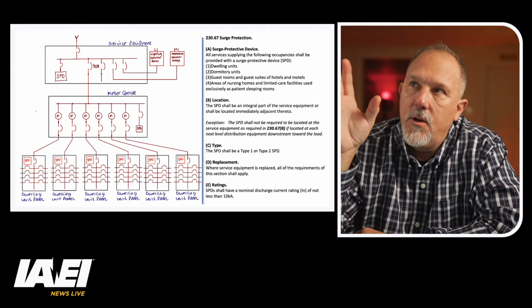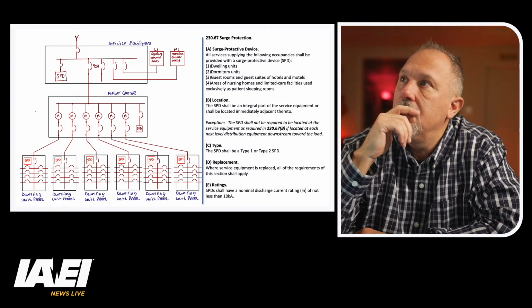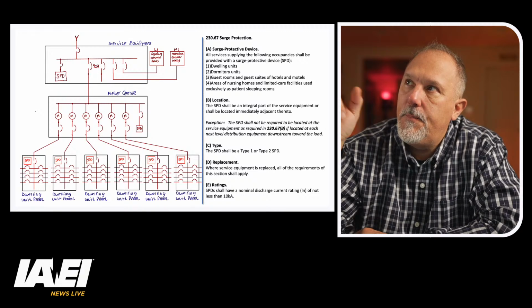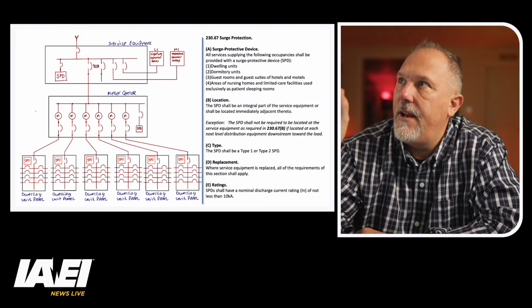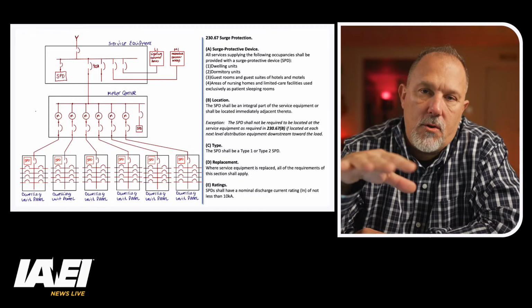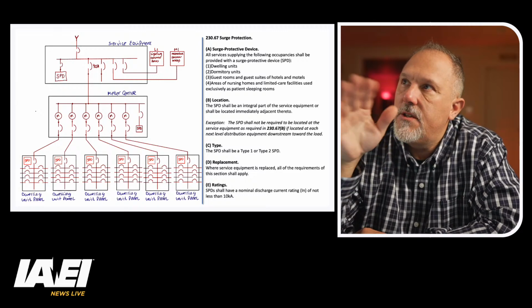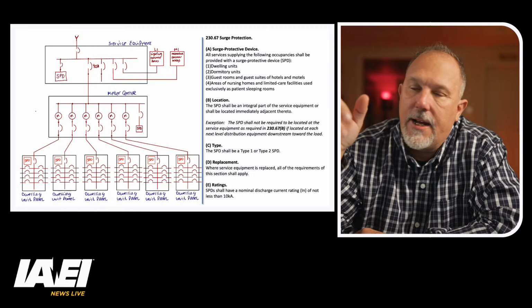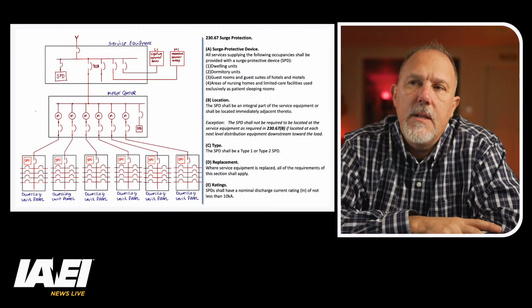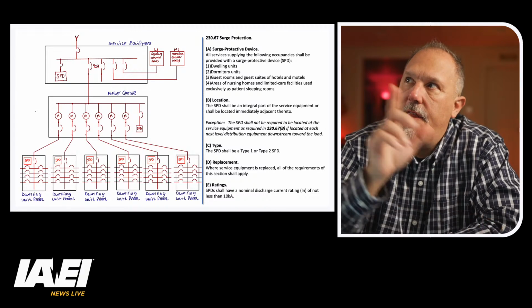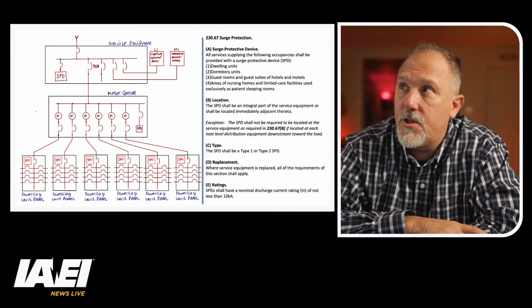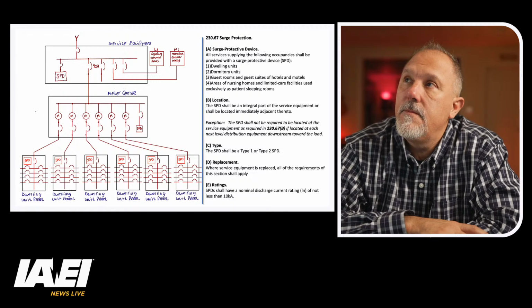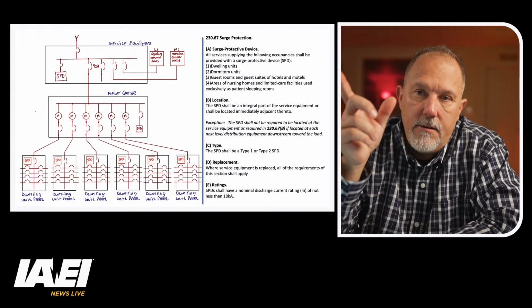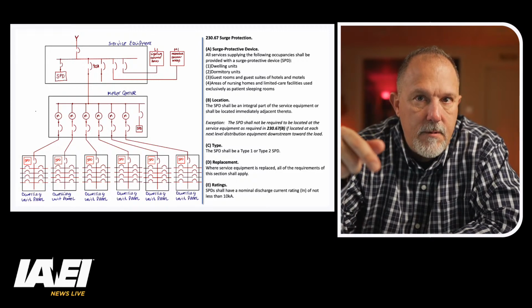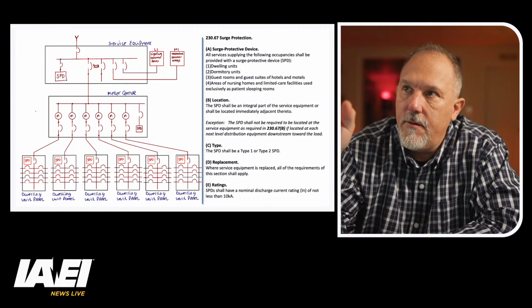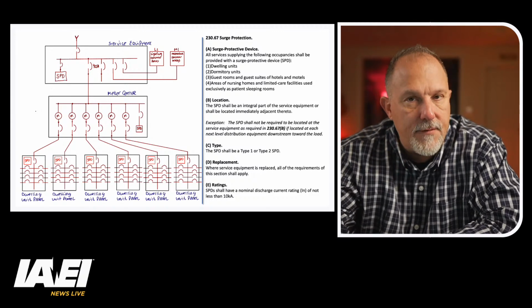You had your service equipment, which was say a large switchboard. Off of the switchboard, they fed some panels for common areas, for lighting and for mechanical, like your HVAC, your chiller, or whatever. They came off of that service equipment. I call it an L1 for lighting and an M1 for mechanical. L1 and M1 did not have a requirement for surge, so there was no surge in those two pieces of equipment. The meter center is at the end of a feeder. On the secondary of that meter center are feeders that go to panel boards in each of the dwelling units.